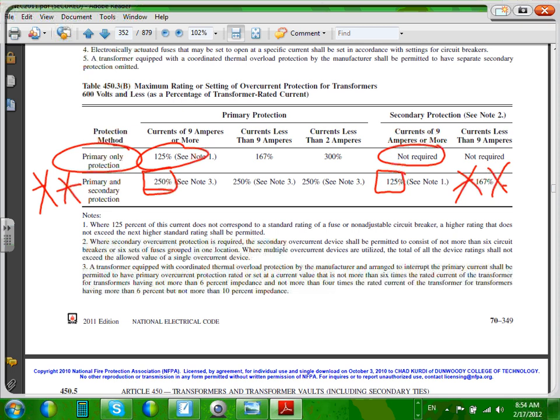There's nowhere to find it. This applies for everything if it's 600 volt or less. The one before it, if one of them, primary or secondary, is more than 600 volt, you go to A. B, if both of them are less than 600 volt. I don't want to go through the details, guys, on multiplication because it will be coming in the industrial. Any comments about this? Comments? I'll show you a calculation based on the bottom one that we did.